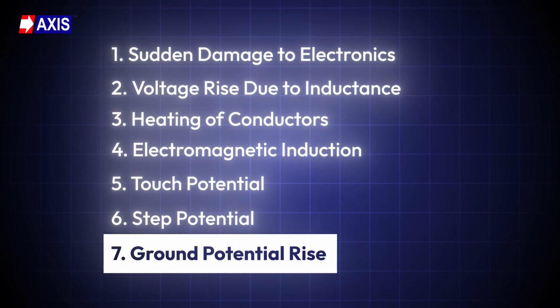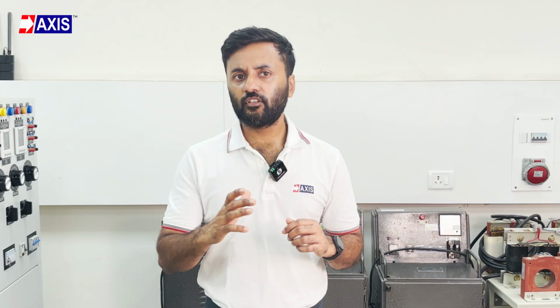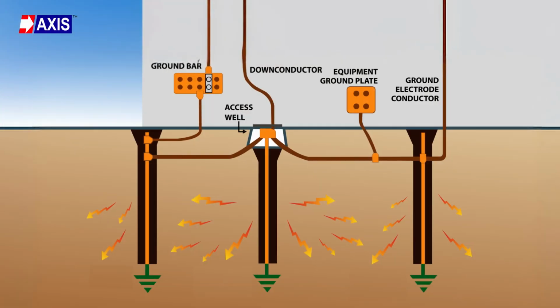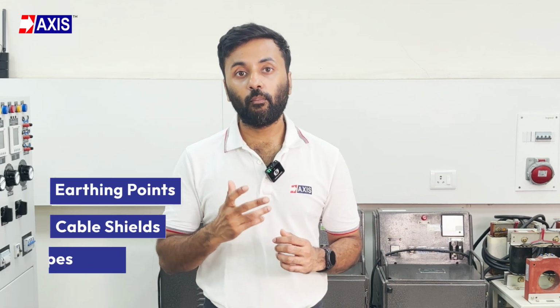Now, seventh, ground potential rise. After a strike, you may notice equipment shutting down, surge protectors getting damaged, or communication systems failing without any visible fault. This happens when lightning strikes the ground near your structure. The current spreads through the soil and raises the voltage of your entire earthing system for a few seconds. That high voltage can enter through earthing points, cable shields, or metal pipes. This sign shows that the strike energy entered from below, not through overhead cables. It affects everything connected to the earthing system.